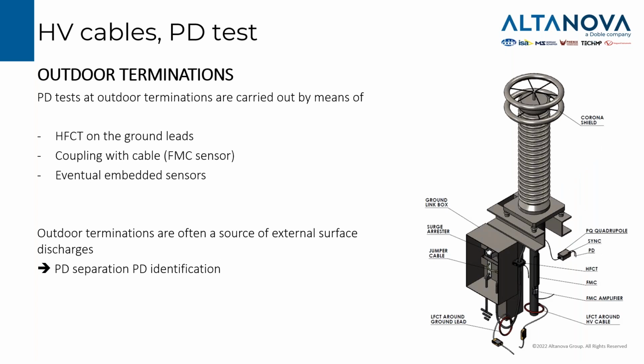When testing outdoor terminations, we can use as well the HFCT high frequency current transformer on the ground leads, or we can take advantage of flexible magnetic couplers along the cable and eventual embedded sensors. A key point for outdoor termination testing is that the outer surface of the termination itself can be a source of external surface partial discharge. Those are partial discharge signals, but they are not occurring inside the insulation. They are occurring in the creepage of the termination bushing. So it's something that is less dangerous with respect to a partial discharge that directly involves the insulation system, something internal to the insulation system. For this reason, we need to separate different PD sources and properly identify the PD sources.